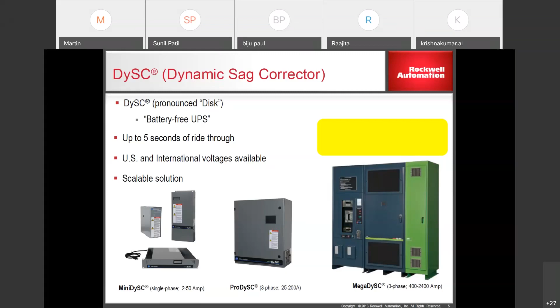So the general features and benefits of the DySC product are listed, like preventing downtime, which means it protects against short-term sags and interruptions that can shut down production. So it protects even from a 0-volt condition. This point becomes very significant because we are talking about a solution wherein there is no battery involved. So everyone will have that doubt in their mind: without a battery, how is the system going to sustain? Of course, when the line voltage is available at 50% of nominal value and above, it uses equipment known as a cross coupling transformer to restore the voltage back to nominal, up to 5 seconds without any consumption of onboard stored energy.